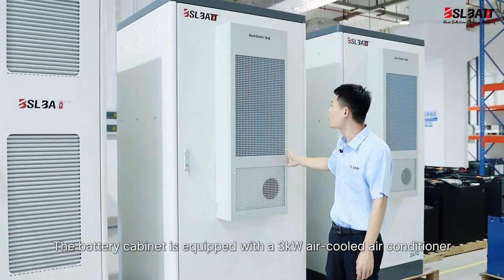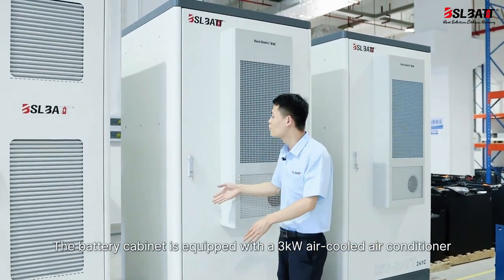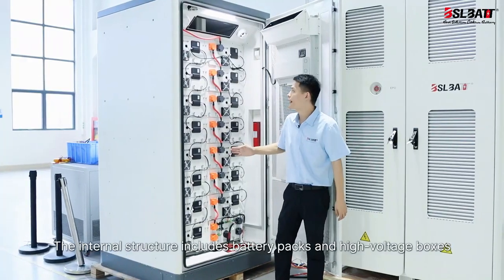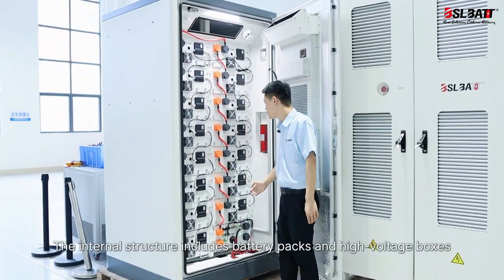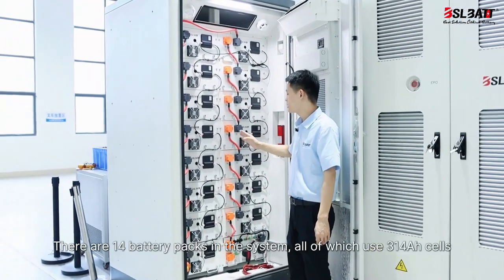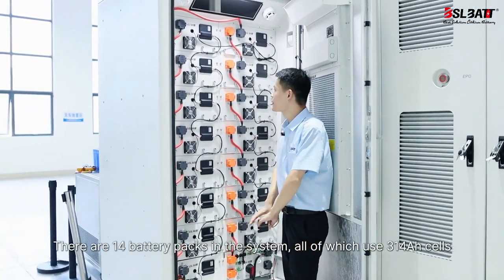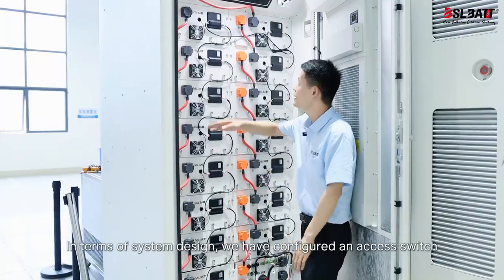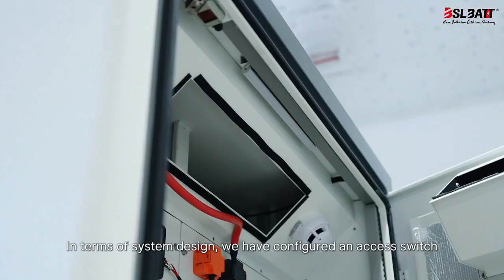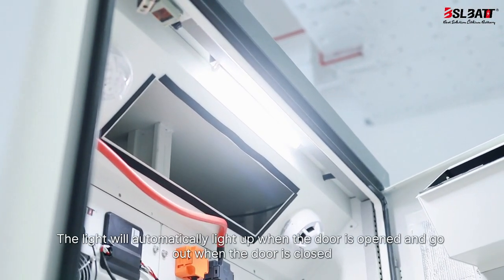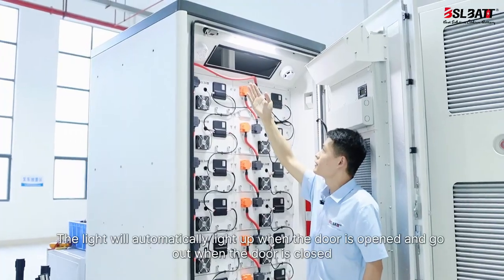The battery cabinet is equipped with a 3 kilowatts air-cooled air conditioner. The internal structure includes battery packs and high-voltage boxes. There are 14 battery packs in the system, all of which use 314Ah cells. In terms of system design, we have configured an access switch. The light will automatically light up when the door is opened and go out when the door is closed.